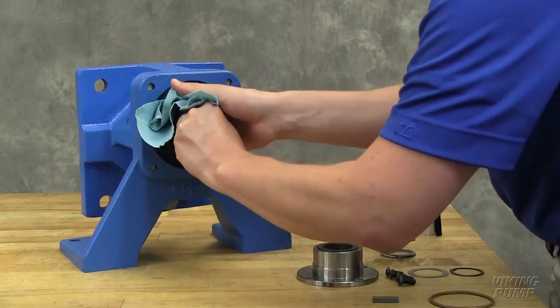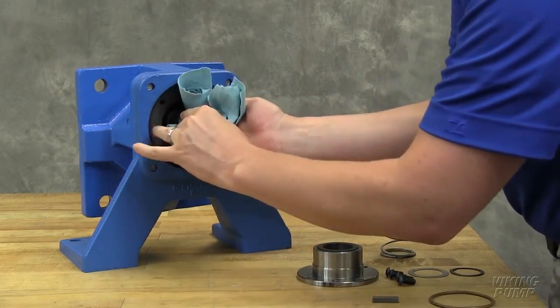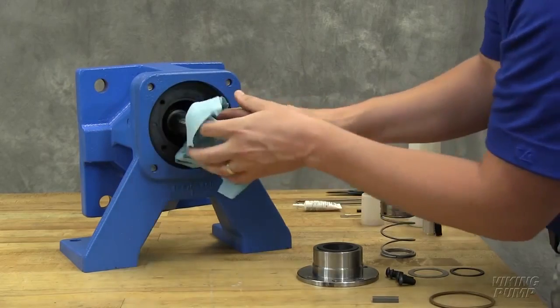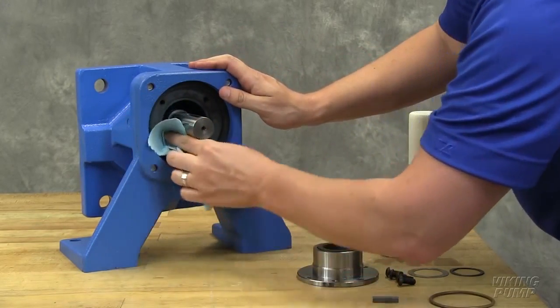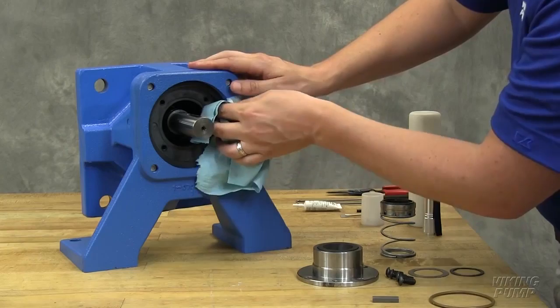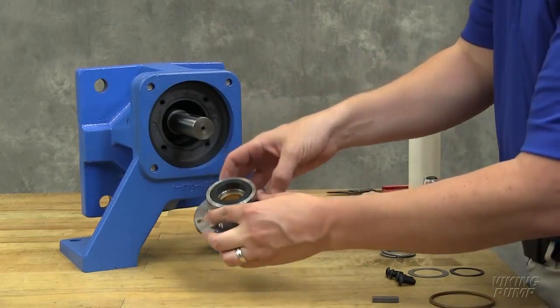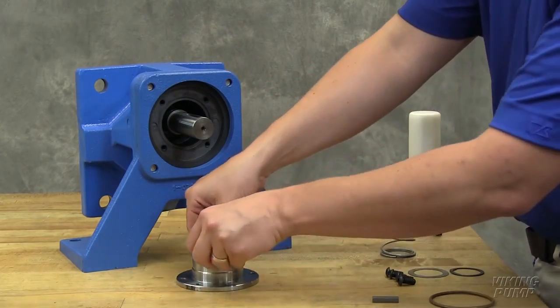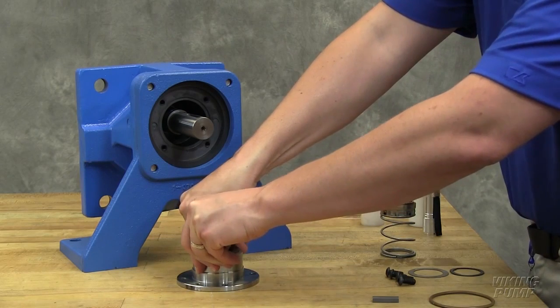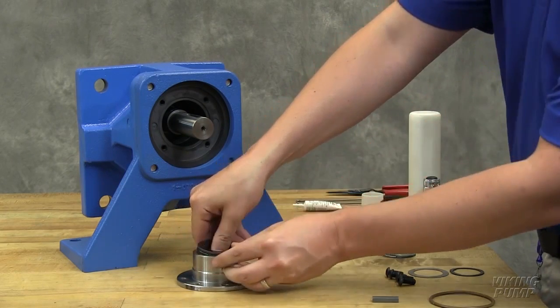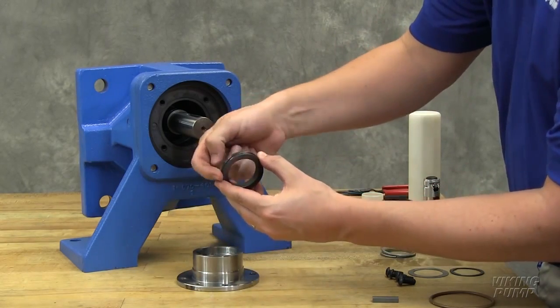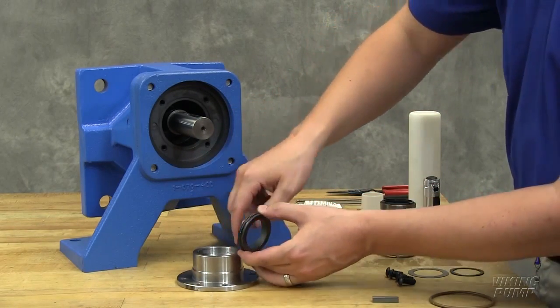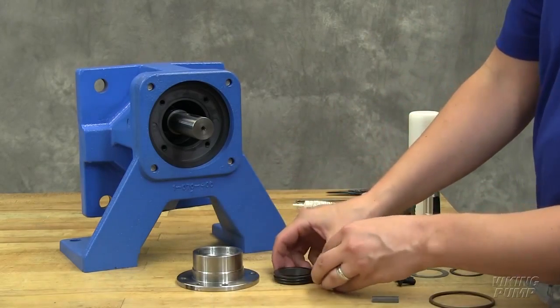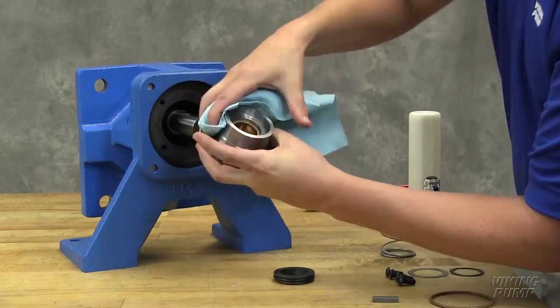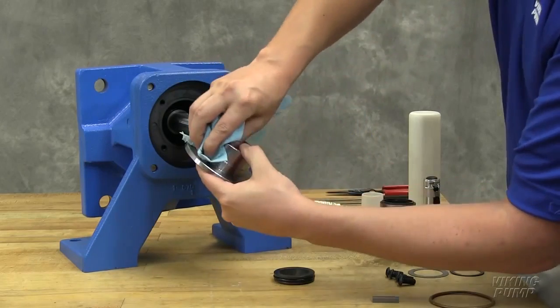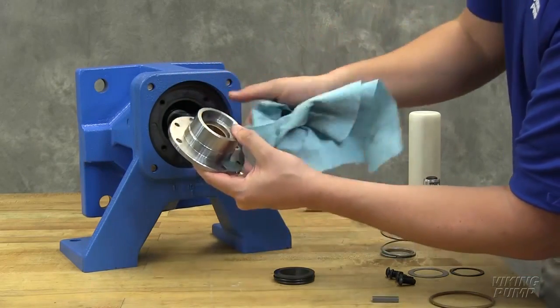Use a lint-free towel to clean the shaft and the seal chamber inside the pump. Make sure both are free of dirt or grit. Also clean the counter bore where the seal holder O-ring is located. Remove the old silicon carbide stationary seat from the seal holder. The stationary seat is a slip fit into the seal holder. The only resistance to its removal will come from the O-ring on the outside diameter of the stationary seat. Once the stationary seat has been removed, clean the inside diameter and outside diameter of the seal holder.